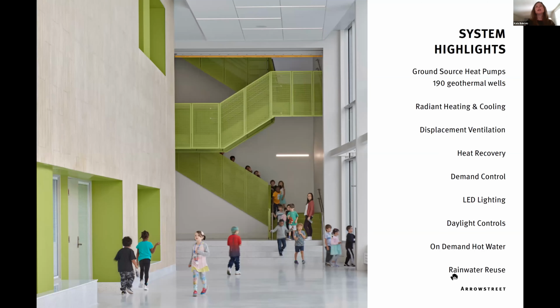Some highlights of the mechanical, electrical, and plumbing systems. The main piece here is the ground source heat pumps—there are 190 geothermal wells going down approximately 500 feet. I'll show you a plan of where those are going in. That's the main plant for heating and cooling, supplying water for radiant heating and cooling throughout the building. The main ventilation is a displacement ventilation system, and similar to what Jacob was talking about, the biggest efficiency piece here is decoupling the heating and cooling from the ventilation. We're doing it a bit differently since it's a different use type than his project, but the main piece is still having heating and cooling separate from the ventilation.